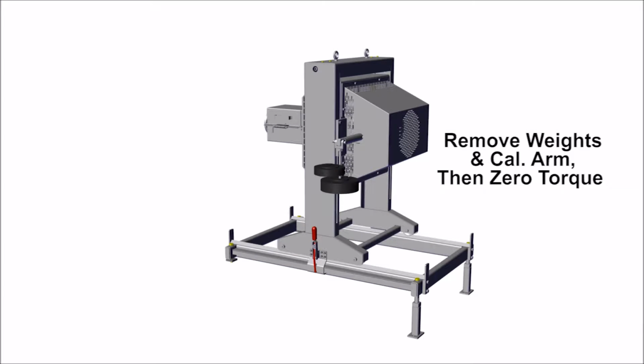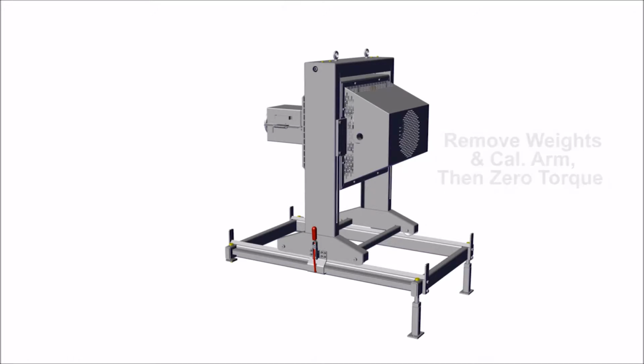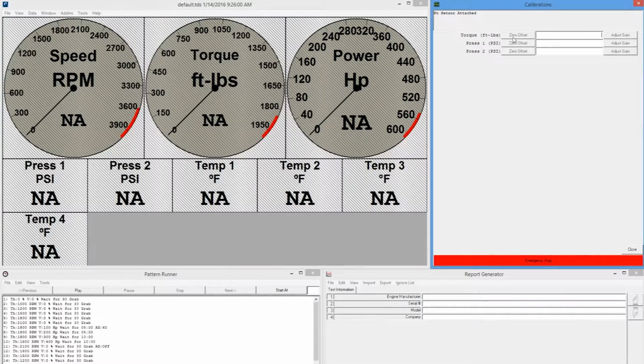To finalize calibration, remove the weights and the calibration arm from the Eddy load unit. Return to PowerNet and zero torque once again.